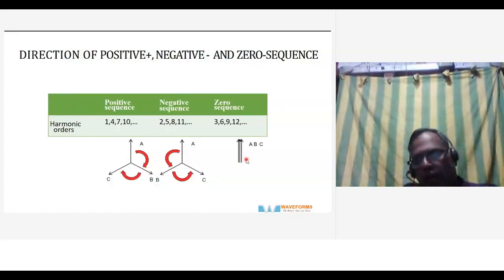When there's unbalance also, we put the unbalanced portion of it close to the neutral current and then add up to the neutral. So that is the slide showing that. So the third harmonic is again a serious issue. Its magnitude is high and it can be very harmful also.